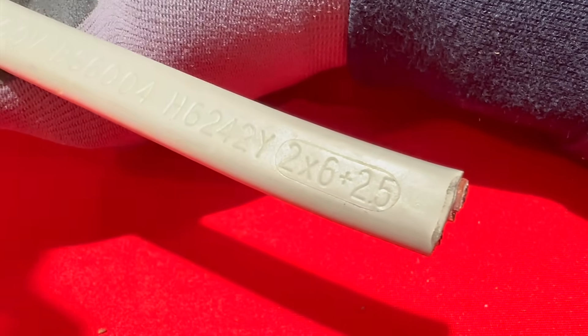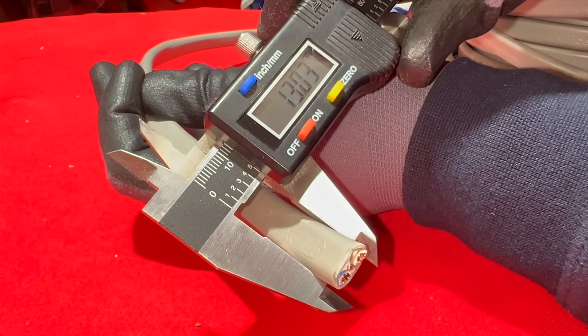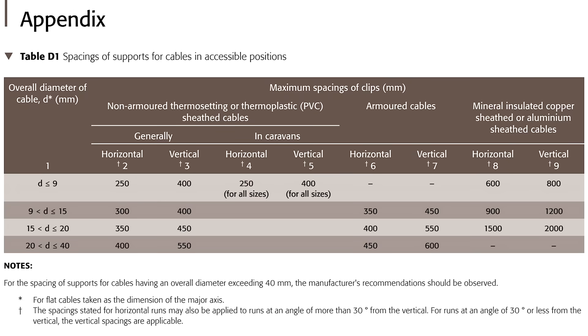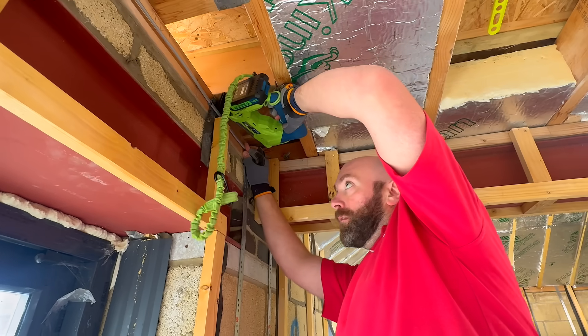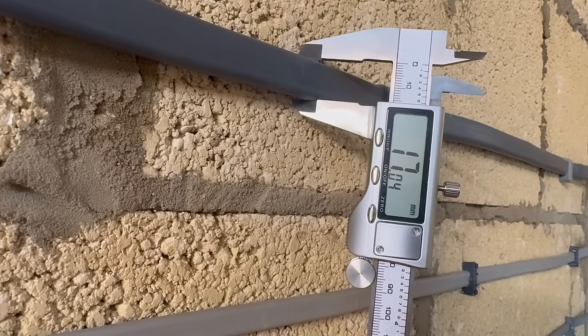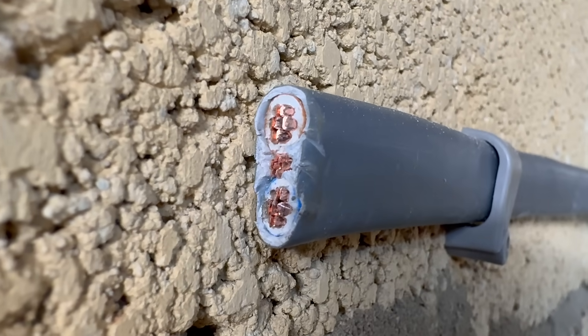6mm² twin-and-earth cable, used for small showers or cookers, is about 13mm across. It's still in the 9 to 15mm band, so the spacing is 300mm horizontal and 400mm vertical. Rigidity means the cable is better at supporting itself. 10mm² twin-and-earth cable, common for induction hobs and larger cookers, is about 17mm wide, so now we're in the 15 to 20mm band. The spacing for this is 350mm horizontal and 450mm vertical. This size of cable is so stiff it can easily bridge wider gaps.